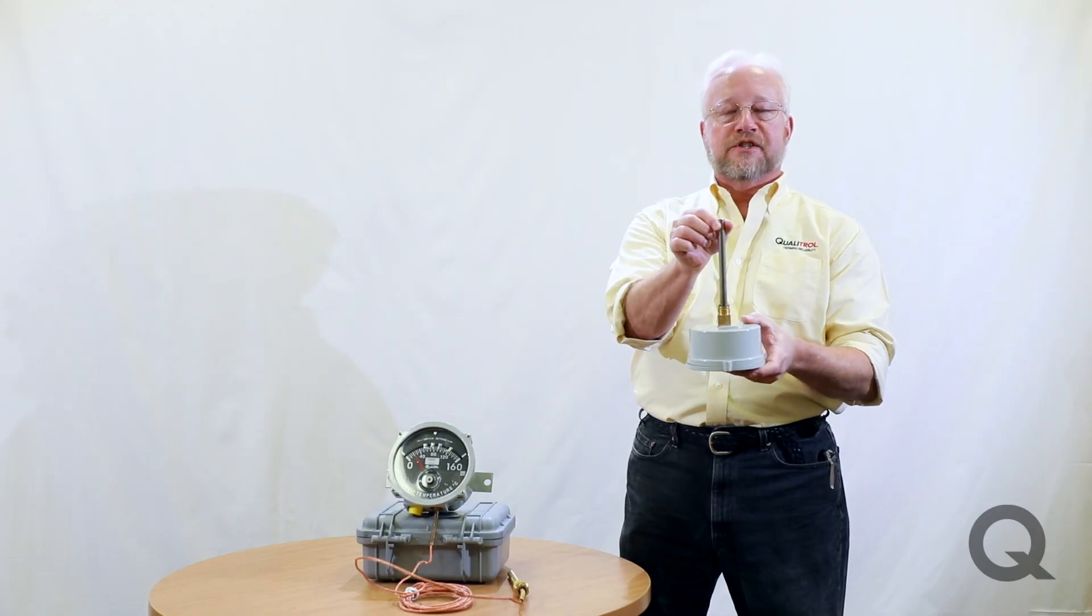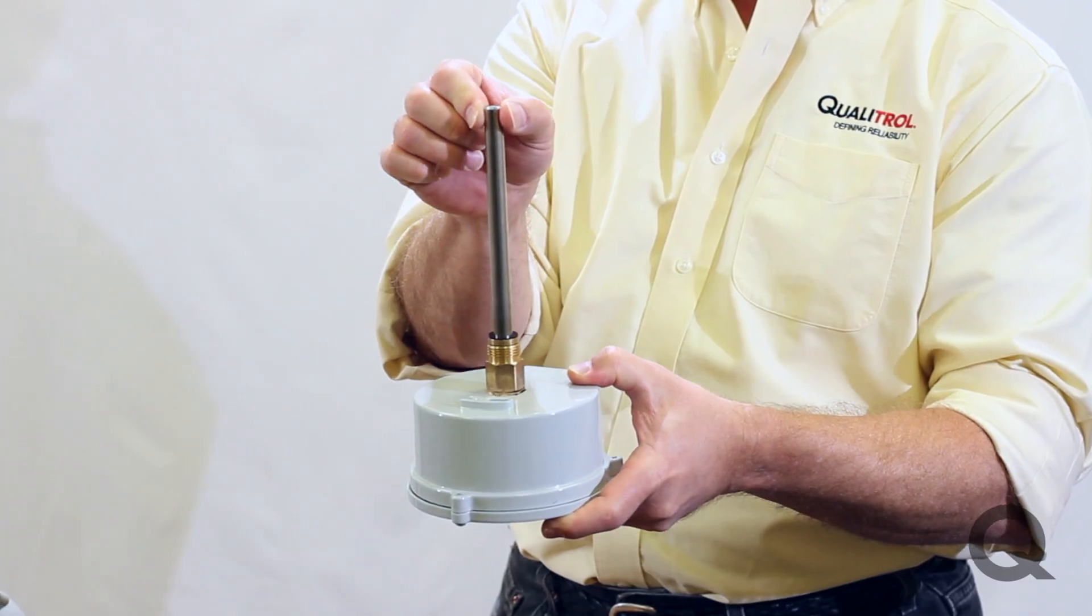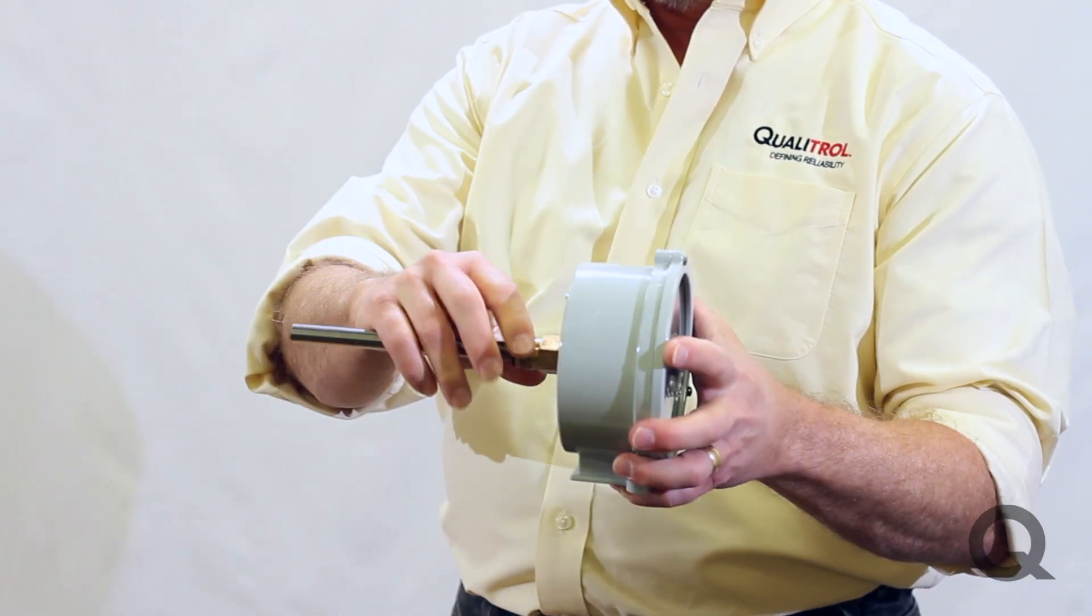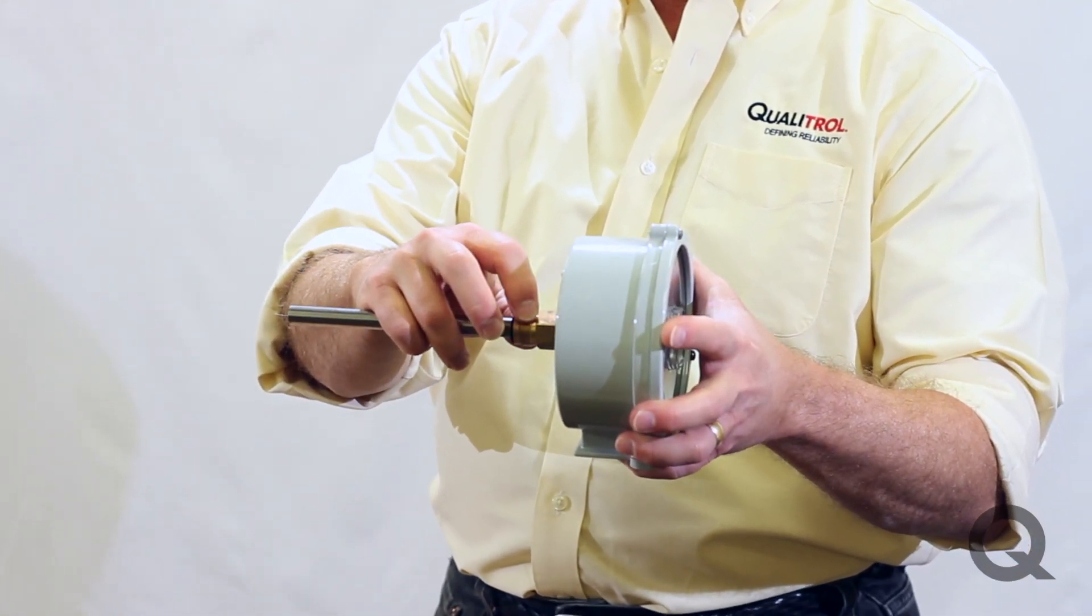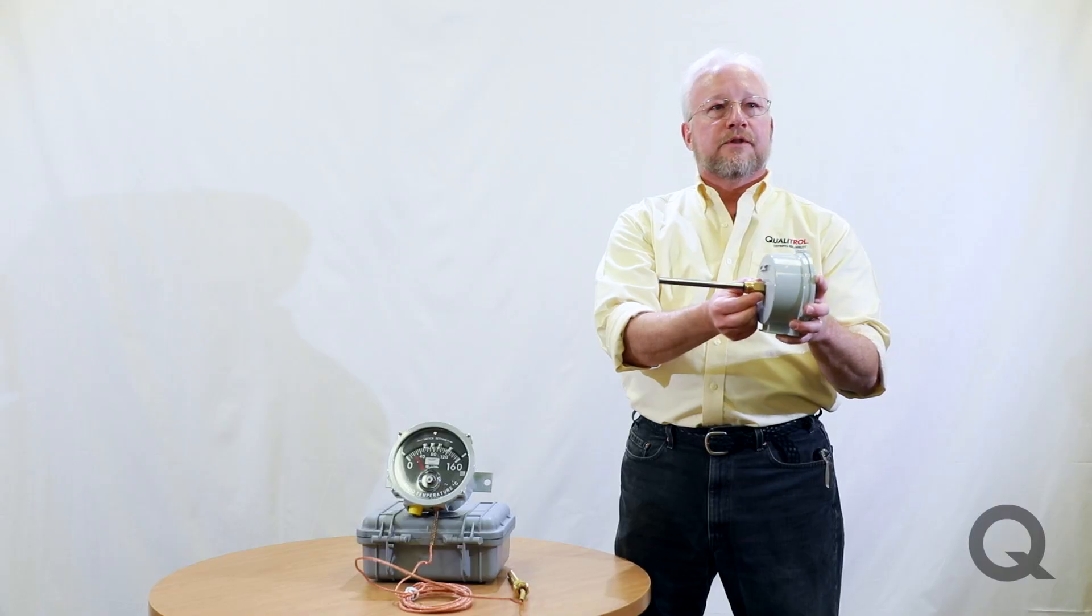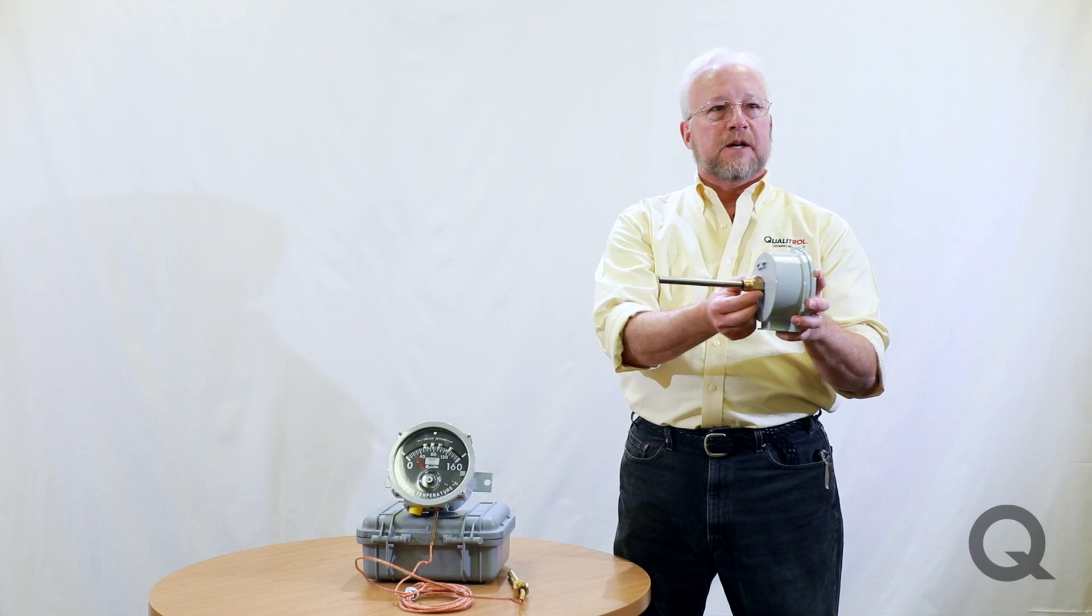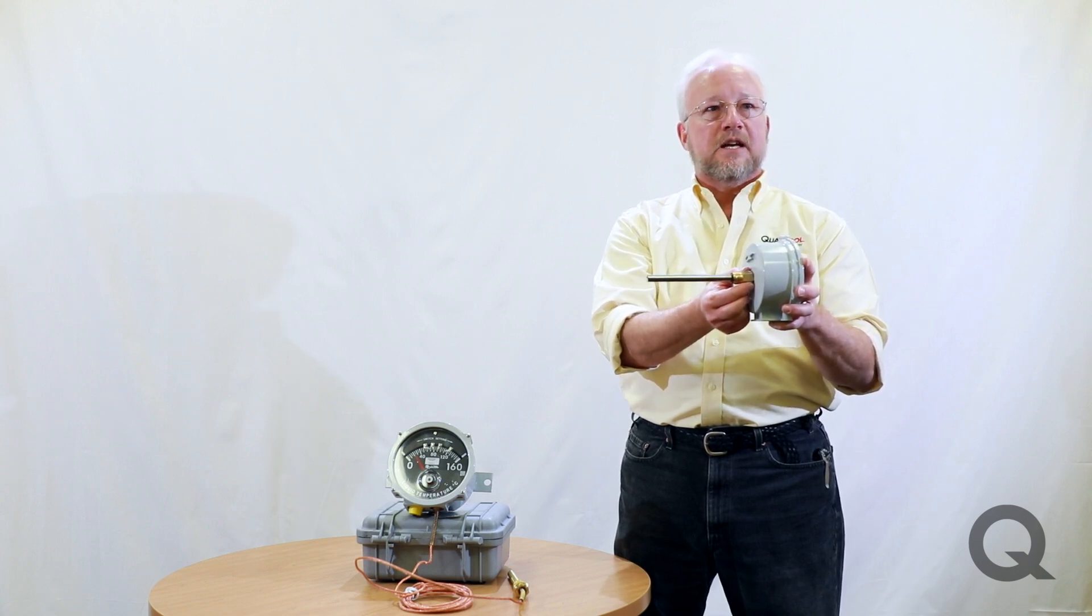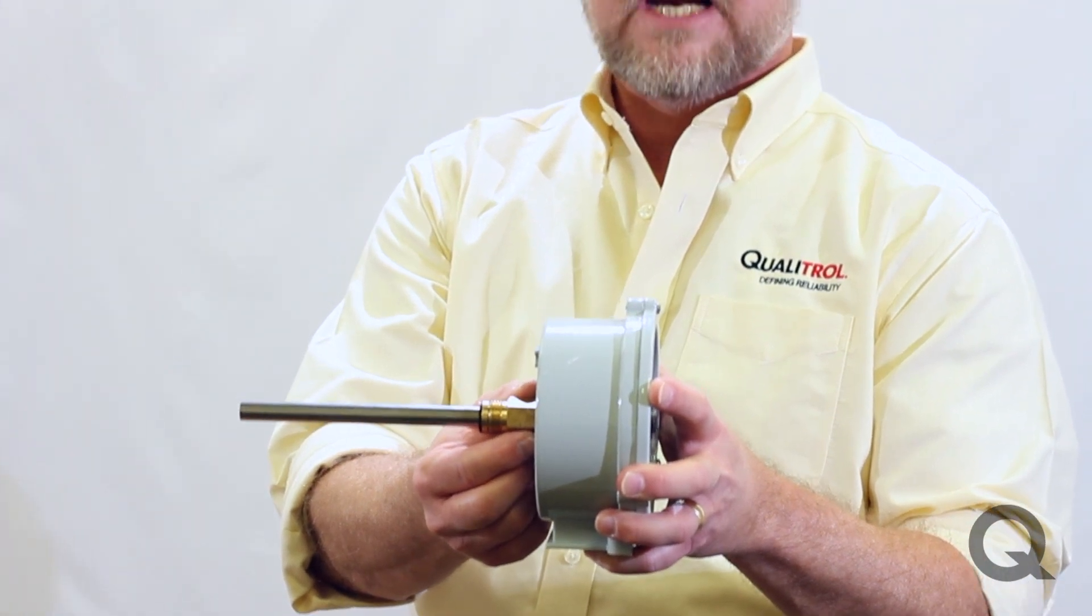The probe diameter is exactly what it says it is. It's the outside diameter of the probe itself. The threads are a little more interesting because you need to know the diameter and the pitch. Typically you're talking 3/8-18 NPT threads or 7/8-14 UNF threads.